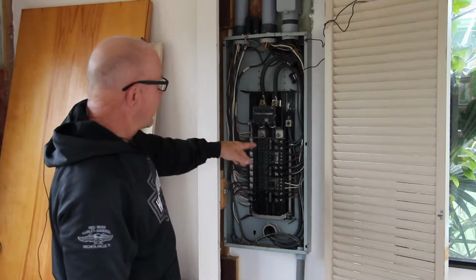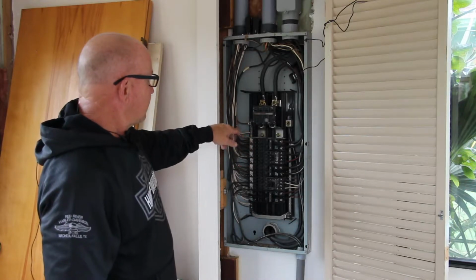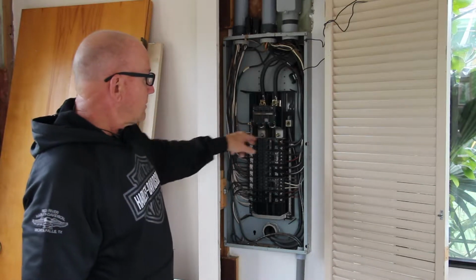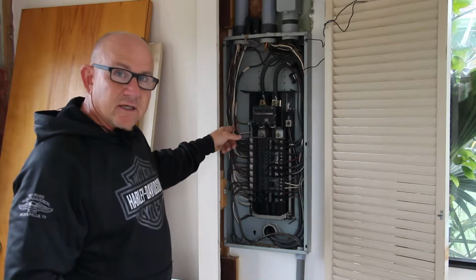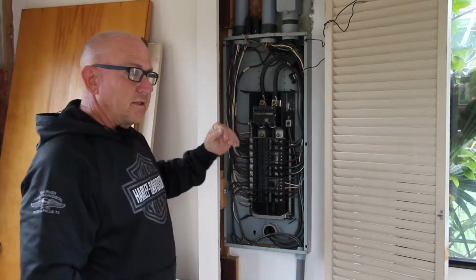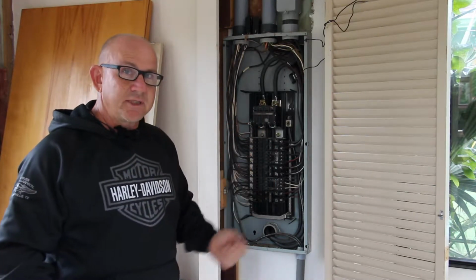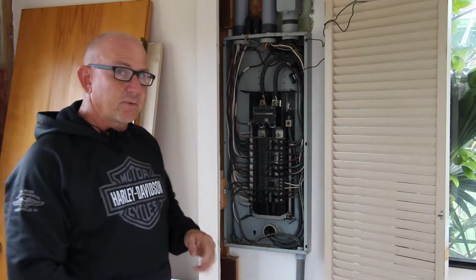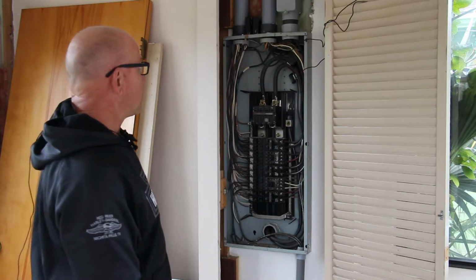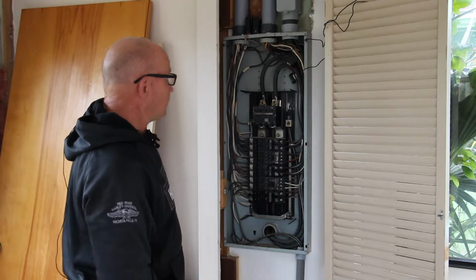We want to make sure that at the main disconnect, our neutral conductor and our grounding conductor are connected. Any other place they're not supposed to be connected, but at the main service panel we want to make sure that they are connected. That is the proper place to ground them.